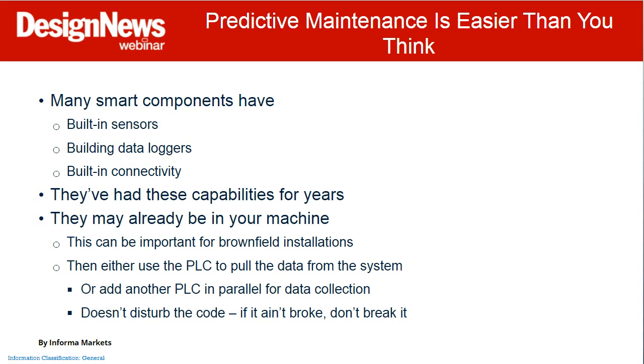But the upside is, we've been talking about those smart components — a lot of this stuff is already built in. You may find out you've already got these capabilities in your drives, in your HMIs, even in your encoders. You've got a drive with a rotating data logger that can store in a rotating buffer and export what happened around a fault, but you can also grab all of this data in advance so you can be analyzing it. So brownfield installations may not be as brown as they appear, and if you already have those capabilities, you can start trying out predictive maintenance or remote monitoring without disturbing your functioning system, which is kind of the gold standard.